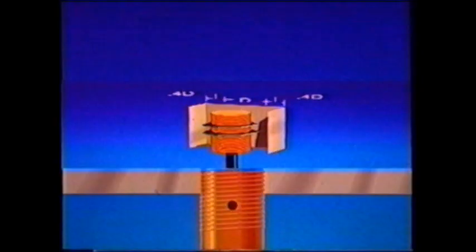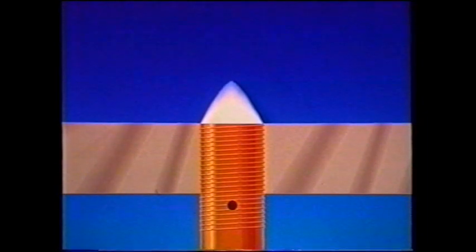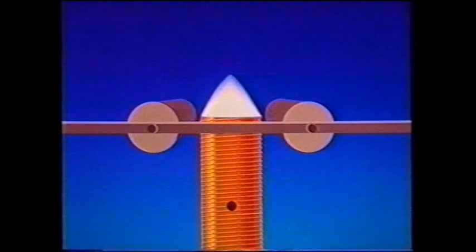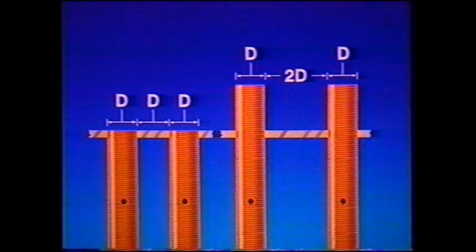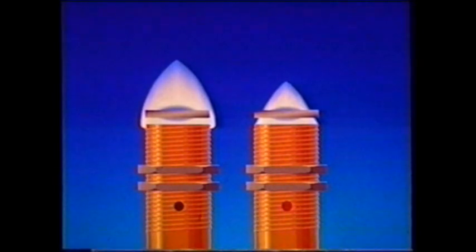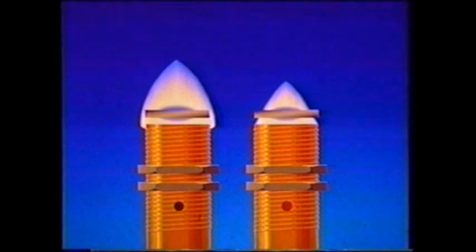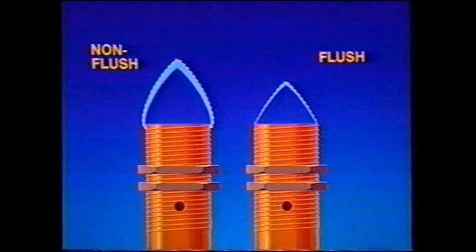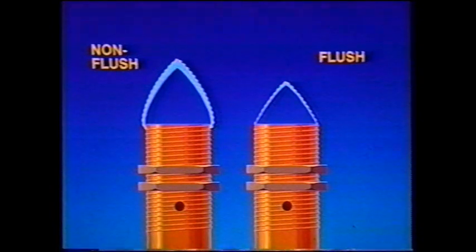A flush switch, because of its narrower active zone, will only sense metal directly in front of the active face. So these switches can be mounted flush with a metal surface for protection of the switch. The narrower active zone makes flush switches a better choice for applications such as sensing through the metal rollers of a conveyor. Flush switches can be mounted closer together without interference between units. Because flush switches have a narrower sensing zone, they are a better choice to use with small targets. Flush switches have less hysteresis — when exact target position is important, use a switch with minimum hysteresis, usually the smallest flush switch possible, and keep the target at 50% of the range.